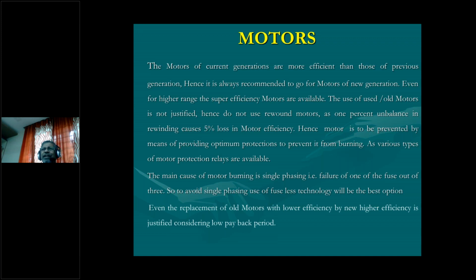This IS standard has the IE1, IE2, IE3, IE4 classes. They have come with the super efficiency motor. Even for higher ranges, super efficiency motors are available. The use of old, that is second-hand, motors is not justified. Hence, do not use rewound motors, as 1% unbalance in rewinding causes 5% loss in motor efficiency. Rewinding, in energy conservation, is not recommended.